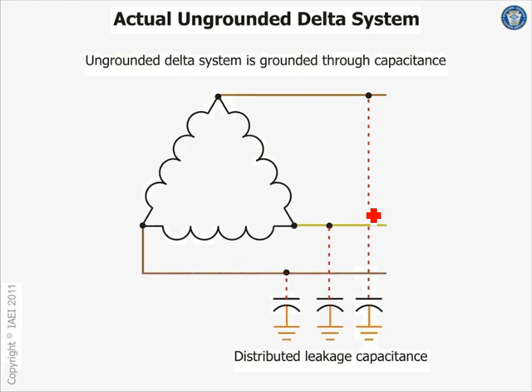It's a big, they call it the pi. If you've heard about the pi analysis, one leg of the pi takes into consideration the air between the transmission line and the ground, that's the capacitive reactance, which creates a problem for you in the power system. It creates a leading power factor.